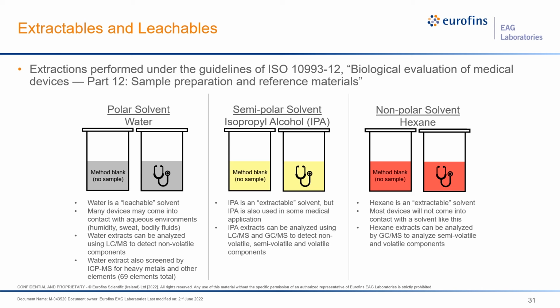When we perform these extractions, we follow the guidelines of ISO 10993 Part 12, Biological Evaluation of Medical Devices, Sample Preparation and Reference Materials. To perform these experiments, we use 3 different solvents that cover a wide range of polarity. So we have a polar solvent, which is water, a semi-polar solvent, which is isopropyl alcohol, or IPA, and a non-polar solvent, which is hexane.